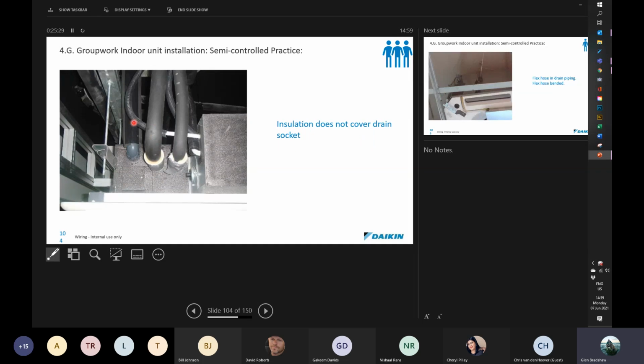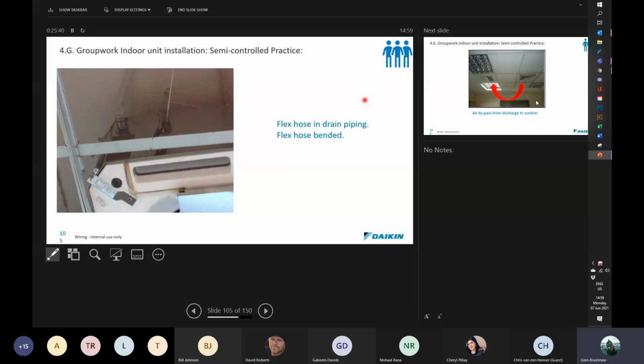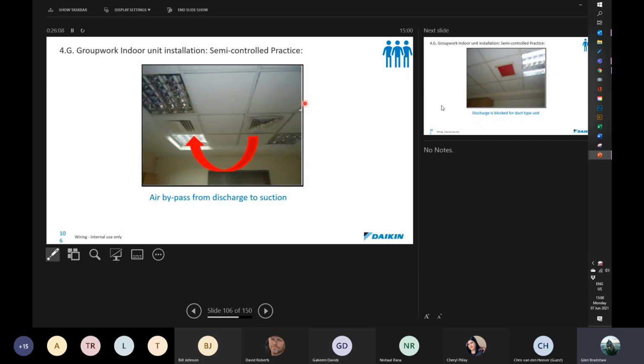Okay, here's another installation mistake. Make sure that the insulation on the drain pipe covers the last elbow if you're using PVC elbows. Otherwise, that is going to start to sweat. Here they've taken the flexible pipe and they've bent it straight away, going straight up. The flexible fitting that is supplied with an air conditioning unit is to give you some linear movement, not angular. Don't turn it into an angle fitting. It's there to allow for some linear lineup, not to be turned into an elbow or 45-degree bend or U-bend or whatever you might choose to do with it.